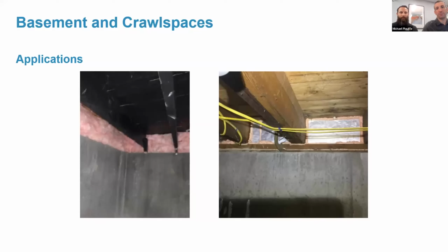Addressing this area of a building will help reduce the stack effect. So we're giving the building fewer areas to draw outside air in through. Energy needs to be consumed to keep that outside air conditioned. So the more we can seal at the near-grade level and at the ceiling plane of the uppermost level, the more we're going to reduce the stack effect in that building, which is what we want to achieve here.